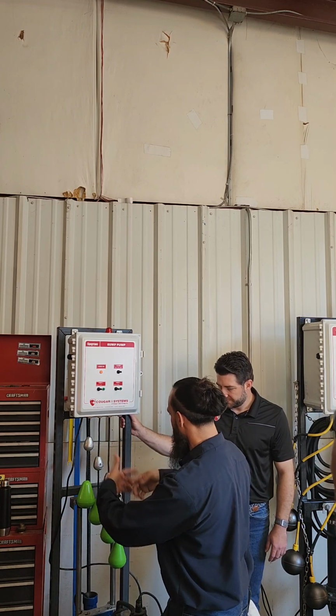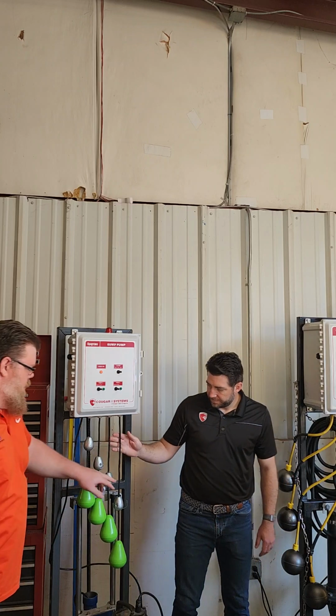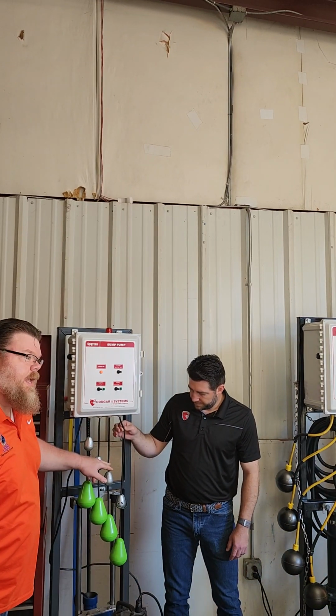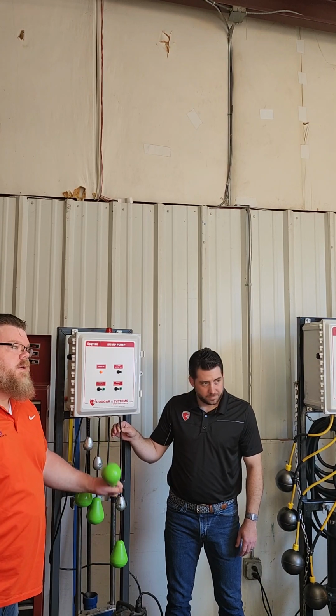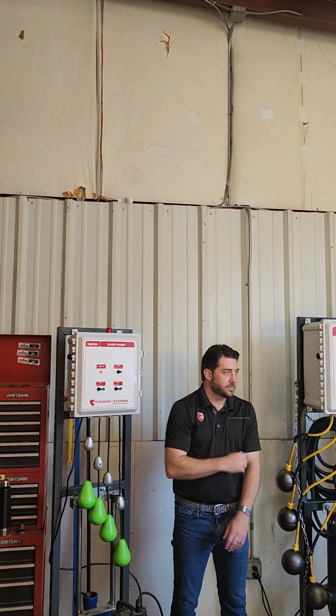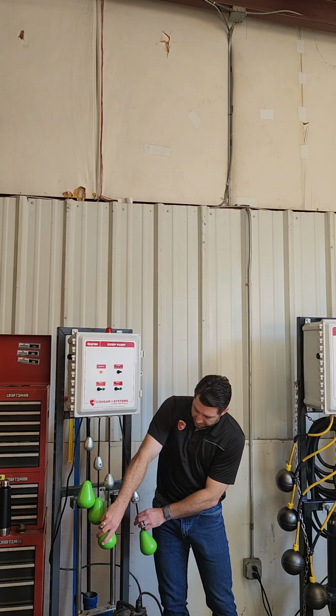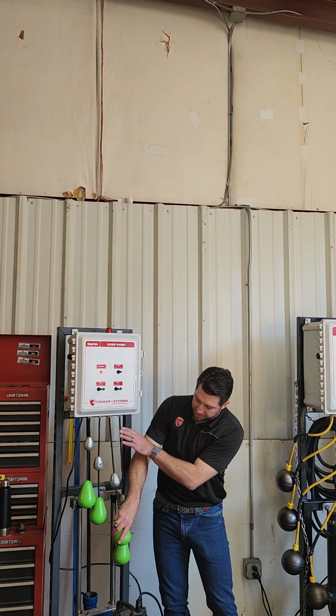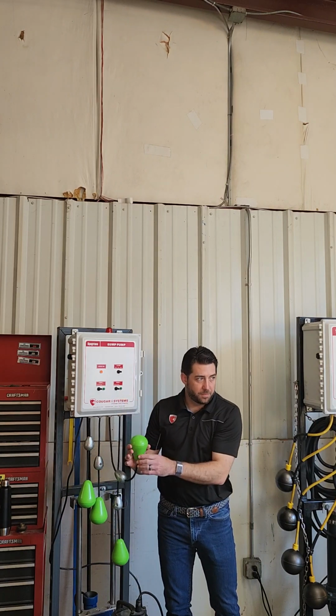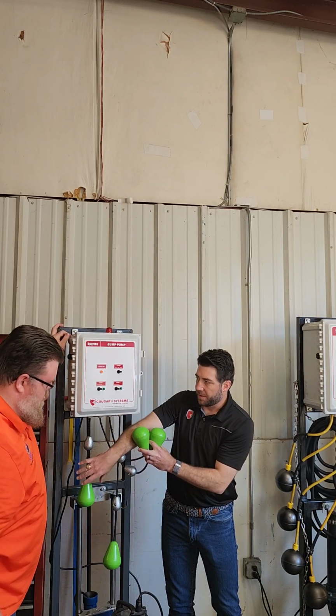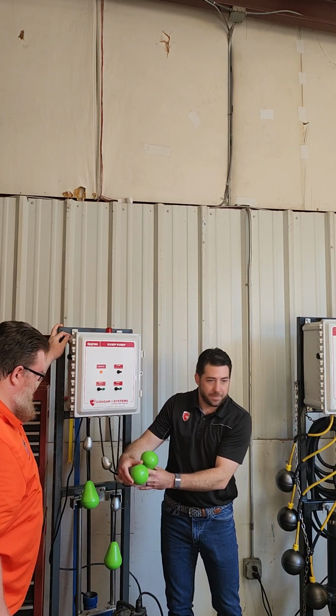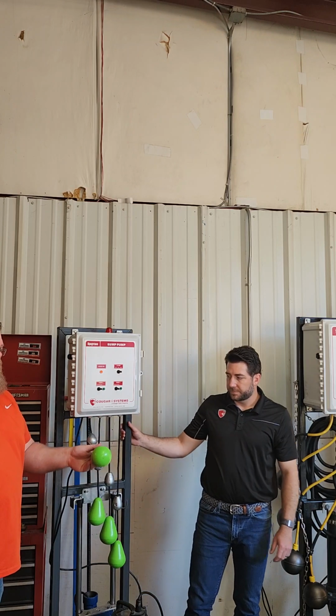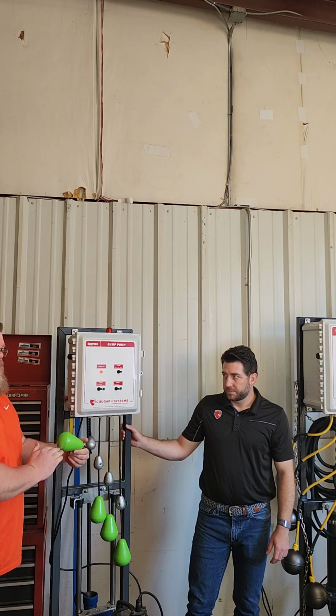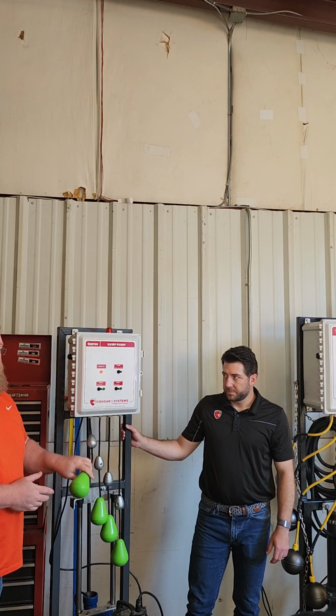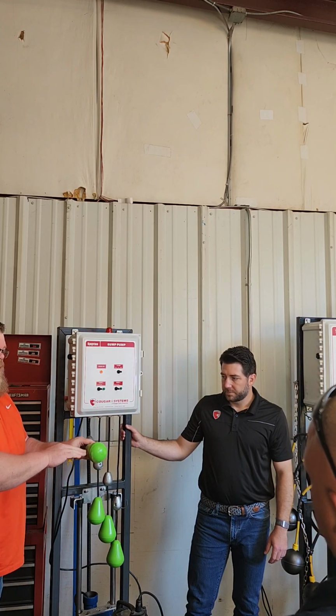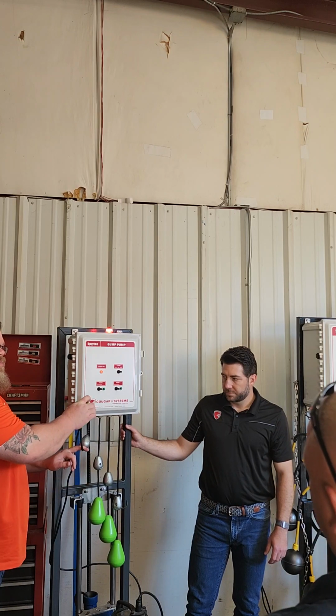Because, like you said, it has to activate each other. Did y'all get that? So this one was zip tied all the way up here, and this one was zip tied here. Now this is acting like your first float. And then it won't turn on because it has to turn on in the right order. Yeah. Right. So if this one was zip tied up there and it was going to wait till the water got up here, and this one tries to go up, you know, the pumps aren't going to turn on. Neither is this one, and then all the way up to the top, you're going to get your high level alarm before anything happens. And these don't really act anything like this. Okay, so they're going to float on top of your water at a level position. They don't start acting until you put it up. So you give it that option to pop up there. But level doesn't work. That's why you have to zip tie it so that this cord will pull it down and get it up like that.